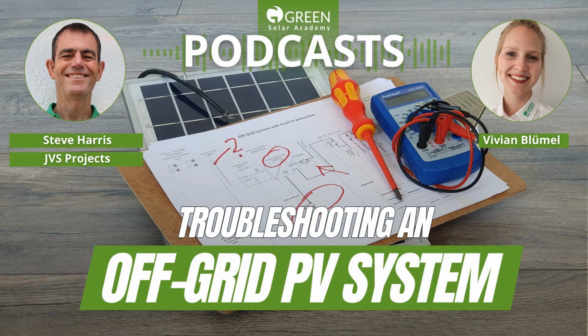I've seen it, where people literally just make their own connections. To those listening to this, an MC4 connector doesn't cost a lot of money. Use the right connections. You'll save yourself a whole world of pain, especially if you've got your panels mounted up on a hot roof. Once you've got a bad connection inside a PV array, inside a PV string, and it's underneath the panels and between the panels and the roof, you're going to struggle to find that. You really are. So do it right the first time. Spend a little bit more money and do it correctly.